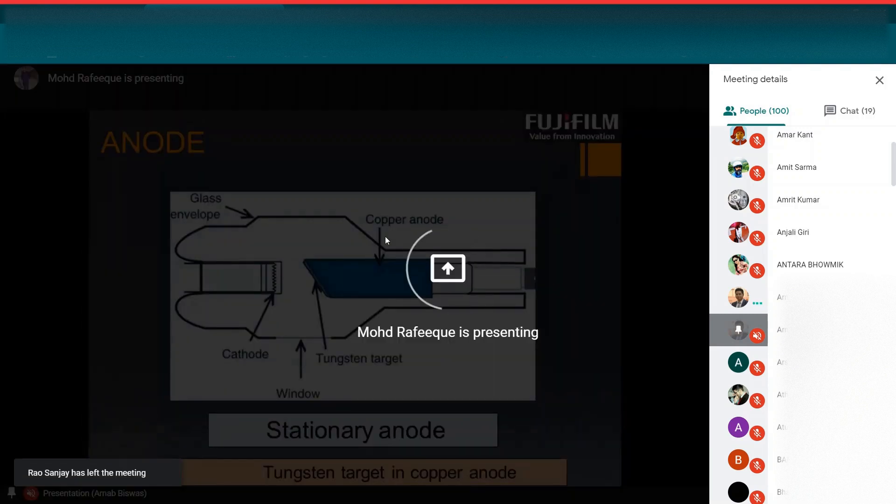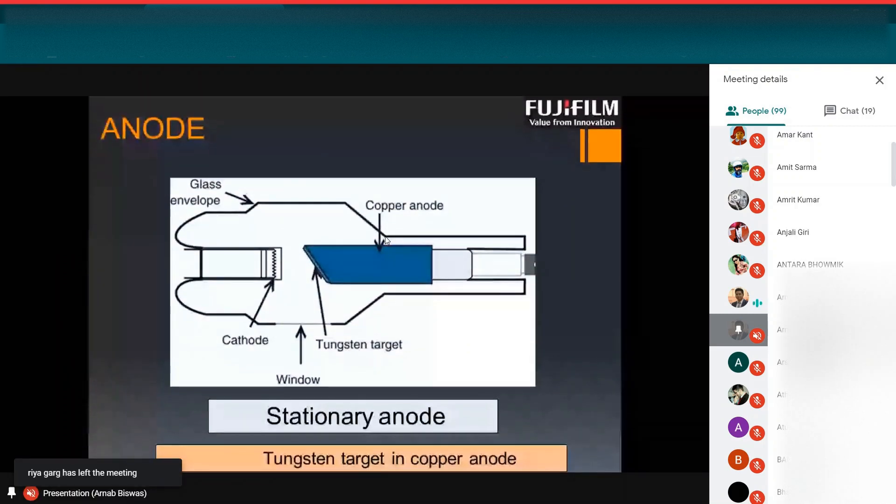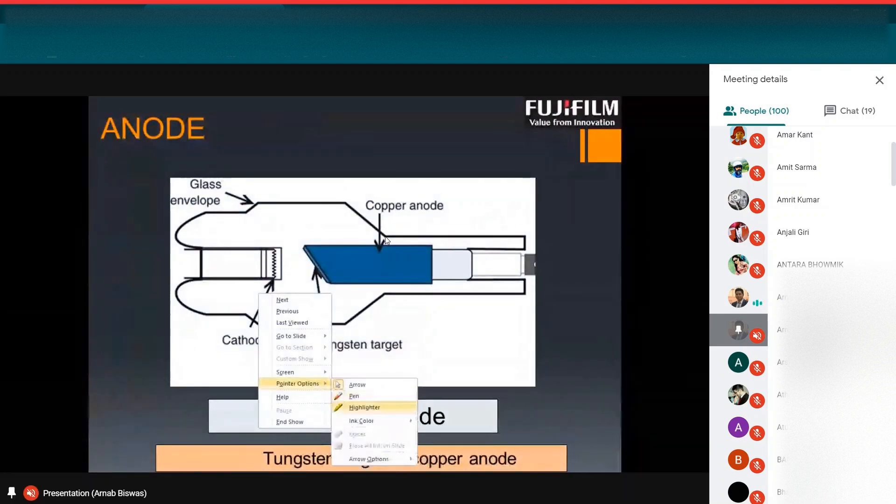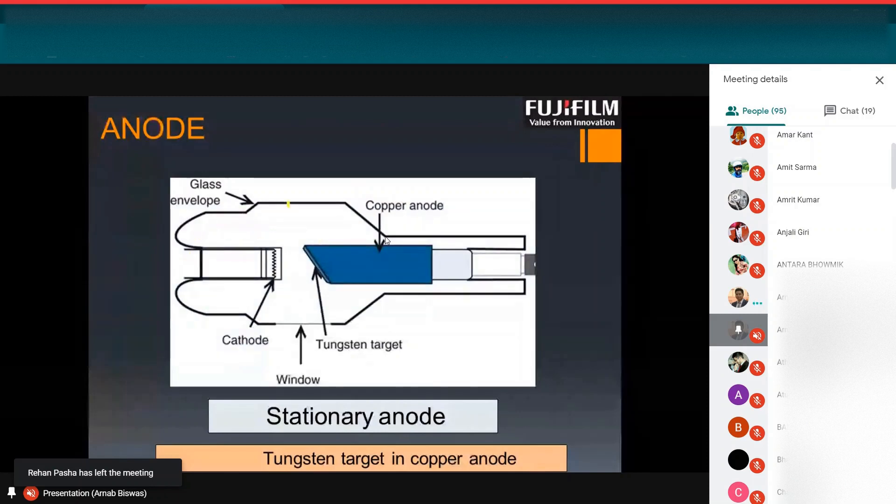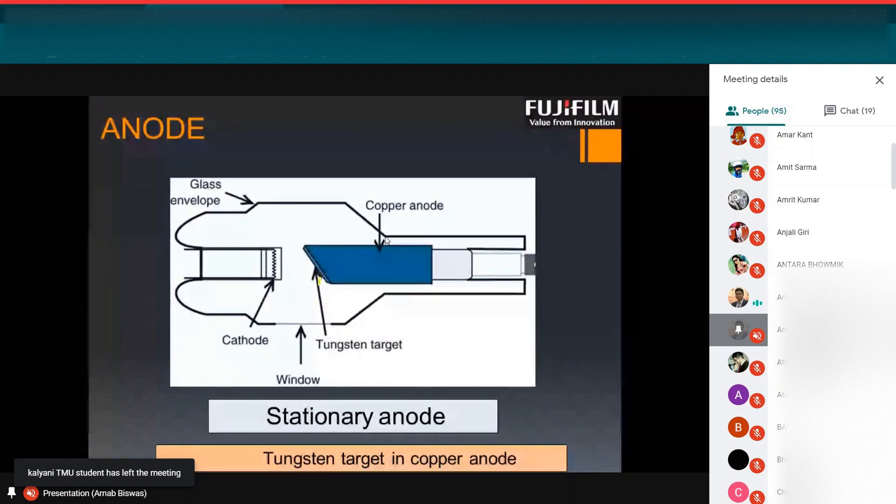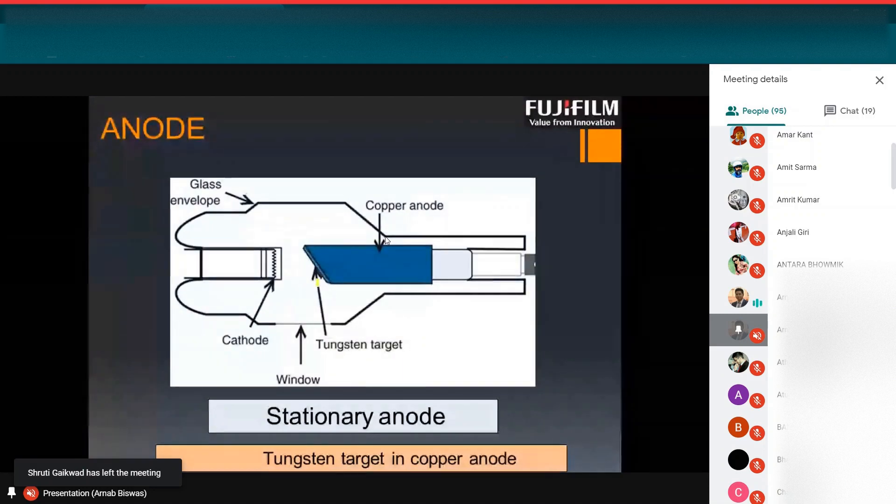In the stationary anode, one tungsten target is used where a copper shielding is placed behind this tungsten target. Cathode terminal is here. There is a window where X-ray beam will flow from there in this window. This is the envelope, glass envelope. And this is a copper anode. Why copper is used behind the tungsten target? Because in stationary anode to dissipate that heat, we use copper. Copper can transfer the heat to the outer side. So to increase the life expectancy of that tungsten target, we use copper as an outer shell.